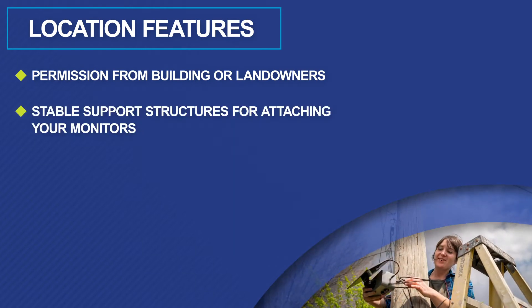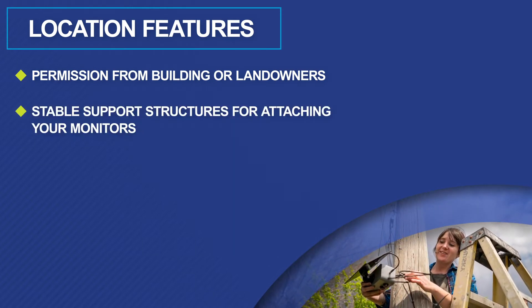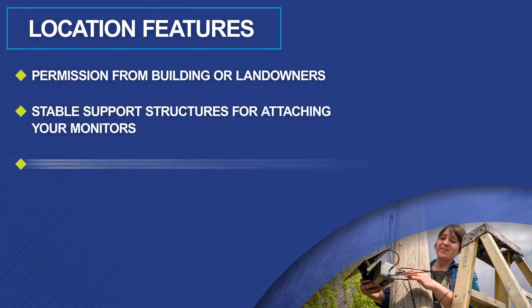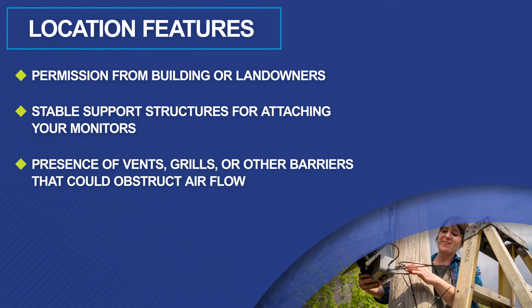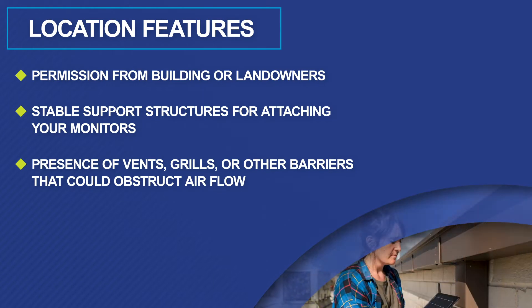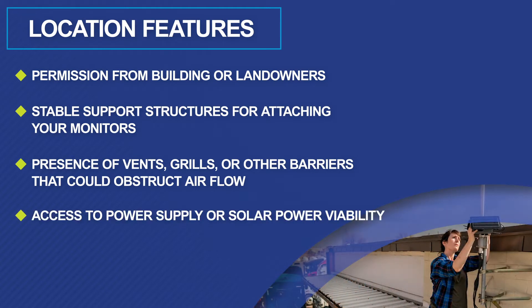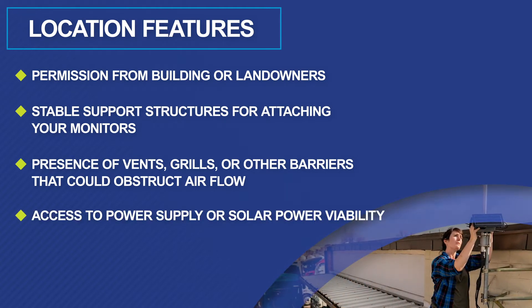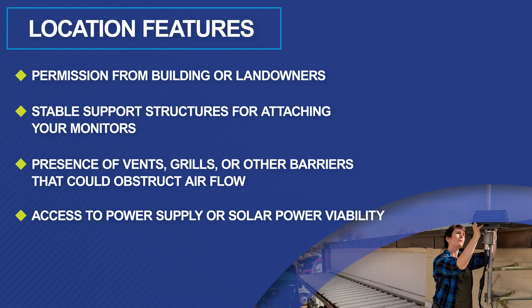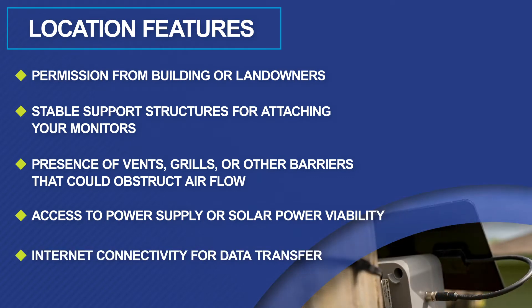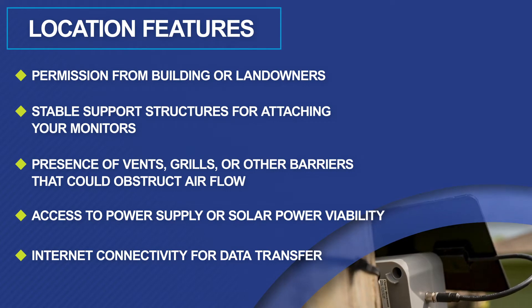Are your monitors attached to stable support structures? Also, are there building structures that could obstruct airflow, such as roof awnings, vents, or other natural barriers? What power source can you tap into? Will you have access to an AC, DC, or solar power supply? What about internet connectivity for data transfer and remote access?